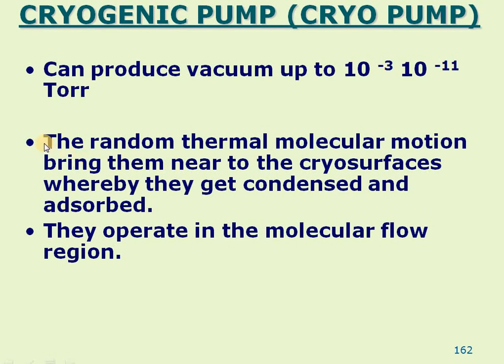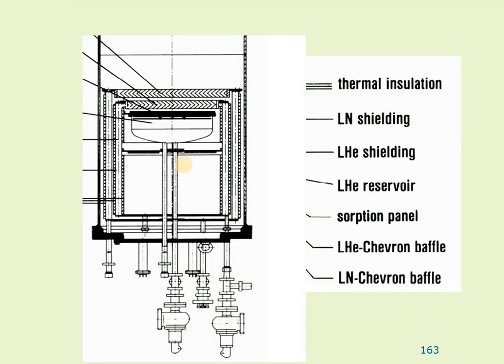The basic physical mechanism is random thermal molecular motion bringing gas molecules near the cold surfaces, where they get condensed and adsorbed — physical adsorption involving Van der Waals forces — in the molecular flow region. This is an advanced, sophisticated type of pump. Prior to operating a cryogenic pump, you must first run a rotary pump to achieve a minimum rough vacuum of around 10⁻³ Torr, then switch on the cryogenic pump.